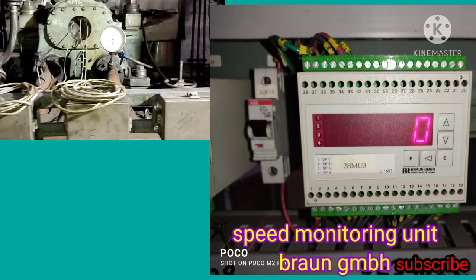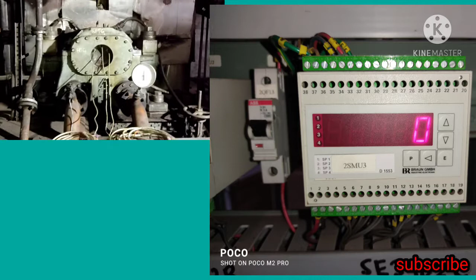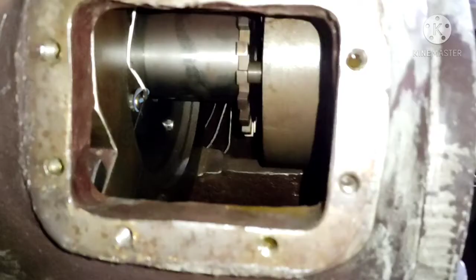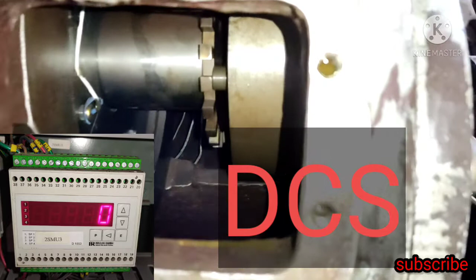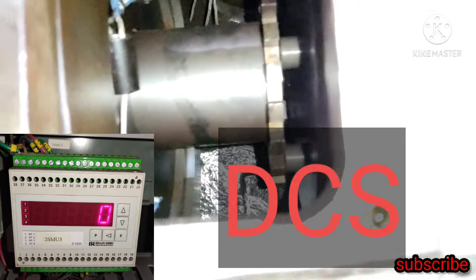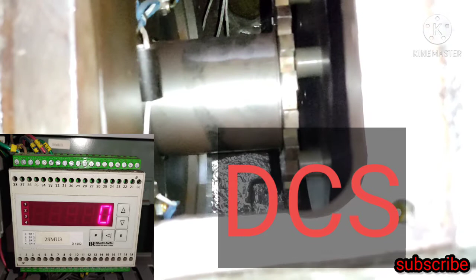This unit shows the speed according to the setting, and in parallel this unit gives an output of 4 to 20 milliamps that goes to our DCS system. This is very essential: this unit accepts the pulsating voltage from the sensor signal, and according to the manipulation and over speed setting, it generates 4 to 20 milliamps.